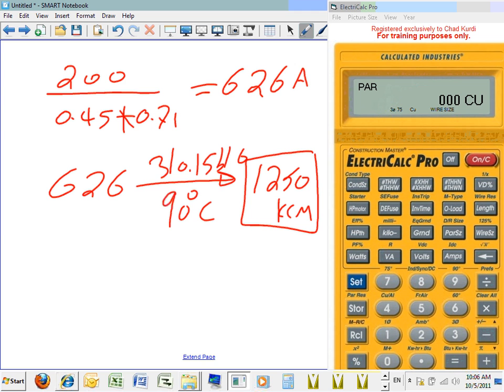You wouldn't group them. So let's go and see if the calculator will come up with the same answer. Shall we? Any question, guys, first about the calculation? Yes, sir. How come you don't count the neutral? Good, very good point. The neutral is only counted if it's carrying other than the unbalanced current between the three phases.